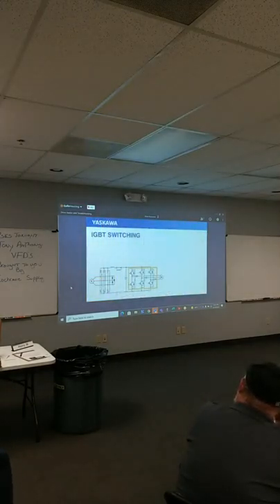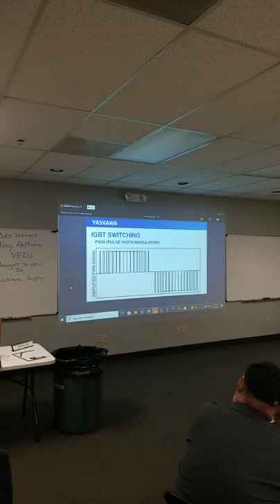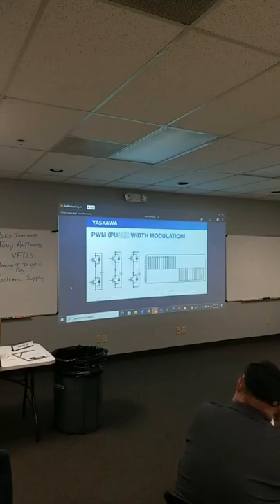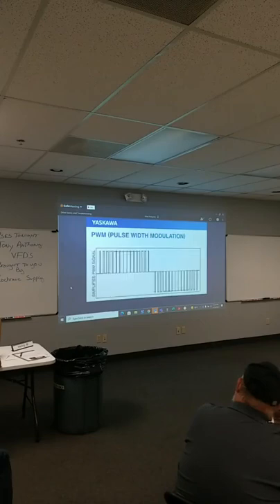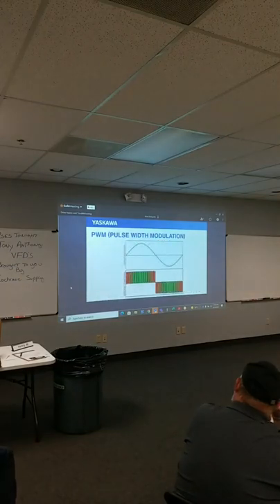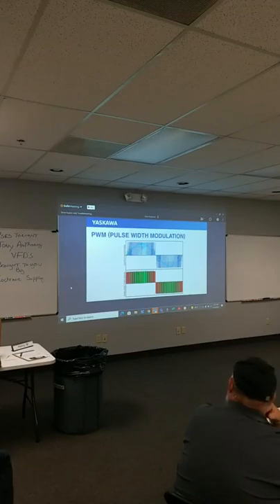The IGBTs are controlled using PWM, or a pulse width modulation scheme. The IGBTs are basically switches that work at a very fast rate. Since they are either on or off, the only thing we can change is the amount of time they are on or off. So, to build this waveform at the beginning, we stay on for a very short period of time. Then we increase our on time relative to the baseline wave we are building from. After reaching the peak, we then start to reduce the on time until the zero point, when another IGBT starts to turn on to create the inverted wave.